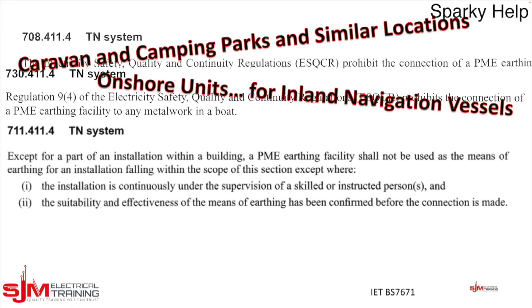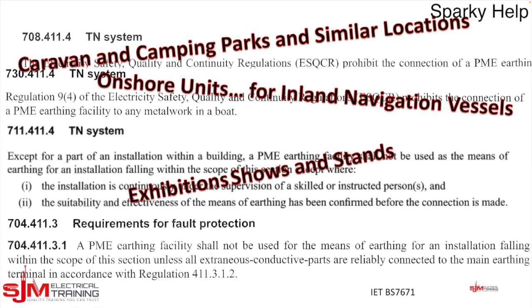It is continually under the supervision of a skilled or instructed person, so that's an electrician all the time, and you've got to make sure that it is reliably connected to earth all the time. So if not, you can't have a PME installation. So where's that from? Exhibitions, shows and stands. Here's another one then. PME shall not be used in this unless it is reliably connected to earth.